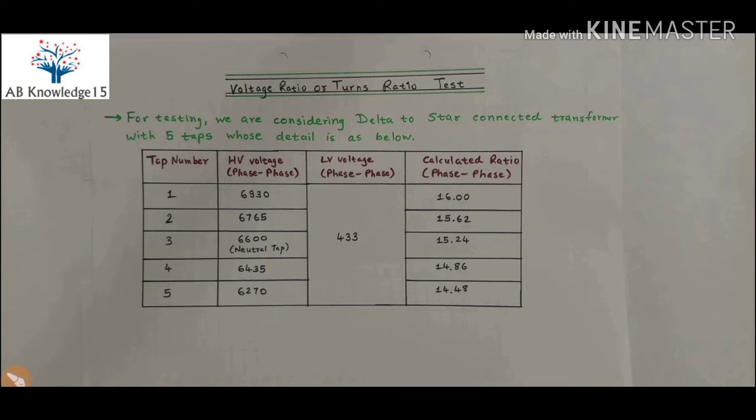For understanding the testing, we are considering delta to star connected transformer with five taps whose details are as below. Here is the transformer with five number of total tappings, and HV side voltages are from 6930 volts to 6270 volts up to five taps. The calculated ratio as per the formula of voltage ratio is from 16.00 to 14.48 from tap number one to five.